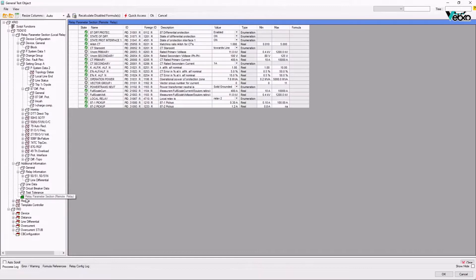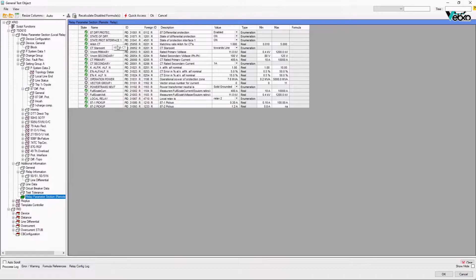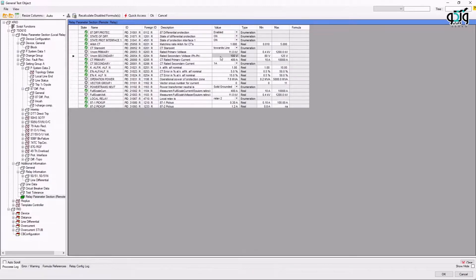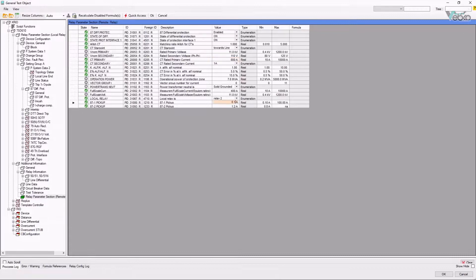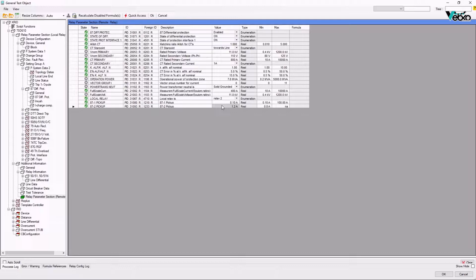In Relay Parameters section, it is possible to view the information related to the relay of the opposite post. Here, parameters with a green check mark in a state section in front of them are the elements that are active in the relay of the opposite side. In this section, it is possible to receive the information about the relay of the opposite side from the setting file, XML file or even orally from the operator of the remote post and enter it into the value field.